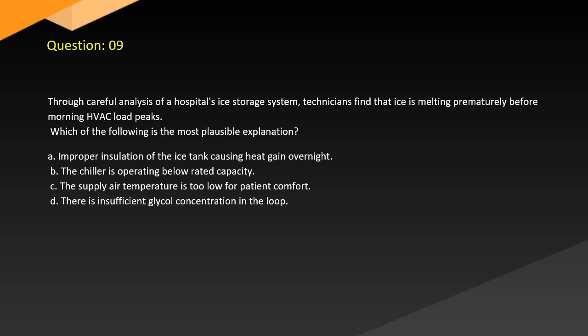Question 9. Through careful analysis of a hospital's ice storage system, technicians find the ice is melting prematurely before morning HVAC load peaks. Which of the following is the most plausible explanation? A. Improper insulation of the ice tank causing heat gain overnight. B. The chiller is operating below rated capacity. C. The supply air temperature is too low for patient comfort. D. There is insufficient glycol concentration in the loop.